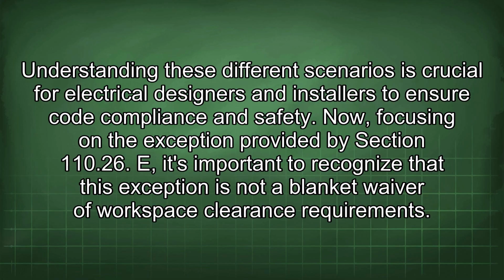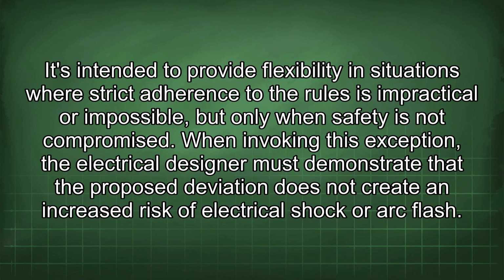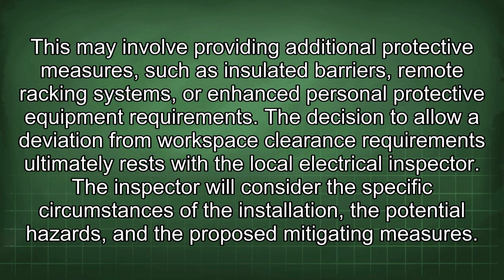Now, focusing on the exception provided by Section 110.26(E), it's important to recognize that this exception is not a blanket waiver of workspace clearance requirements. It's intended to provide flexibility in situations where strict adherence to the rules is impractical or impossible, but only when safety is not compromised. When invoking this exception, the electrical designer must demonstrate that the proposed deviation does not create an increased risk of electrical shock or arc flash. This may involve providing additional protective measures, such as insulated barriers, remote racking systems, or enhanced personal protective equipment requirements.